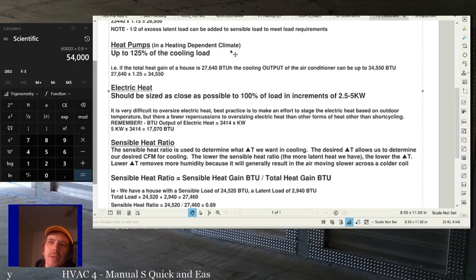But in a heating dependent climate, we do want to try and push the envelope a little bit and oversize that equipment so that we can save energy for those times we are heating. So, you get up to 125% of the load on that, and you probably want to shoot for somewhere close to that most of the time. It's not necessary, but it will, in general, save more money, that energy you save in heating as opposed to the energy you save in cooling.